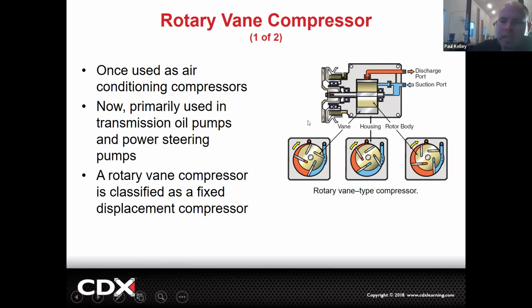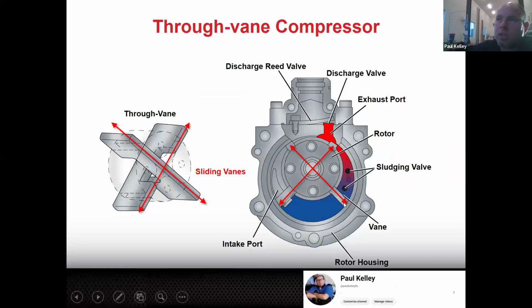Because remember, it's less high and low, it's more suction and discharge. Blue is the suction, that's the low, and orange is the discharge, that's the high. You can see what that kind of looks like here. So as it moves, these vanes have to move. Sadly, though, because they do slide, those vanes will wear.